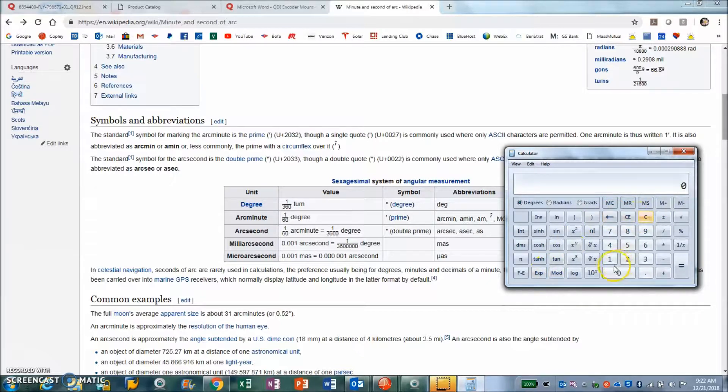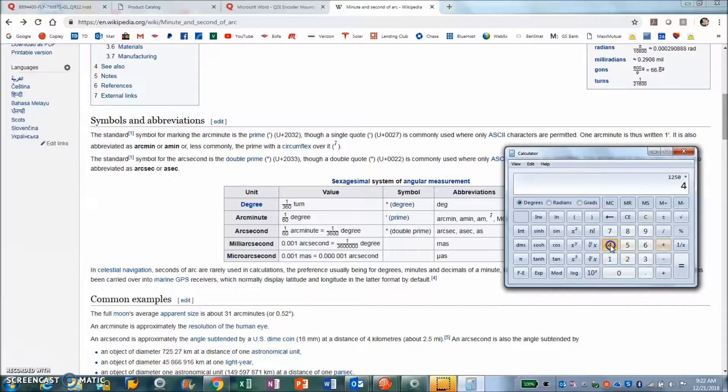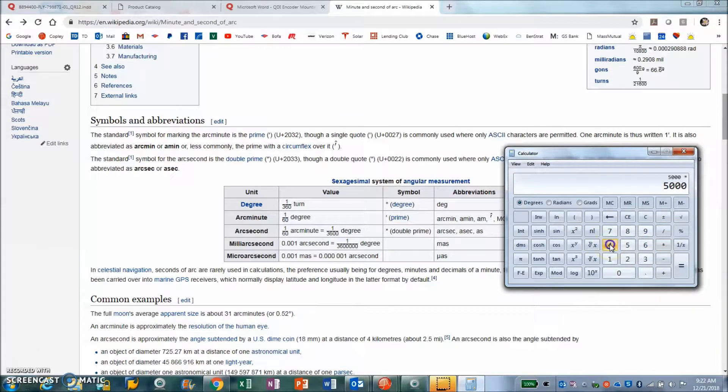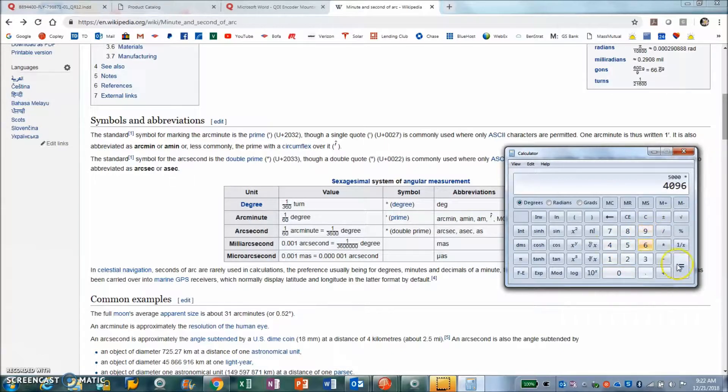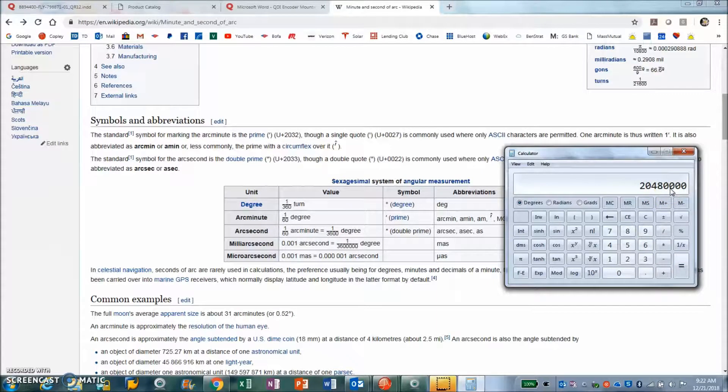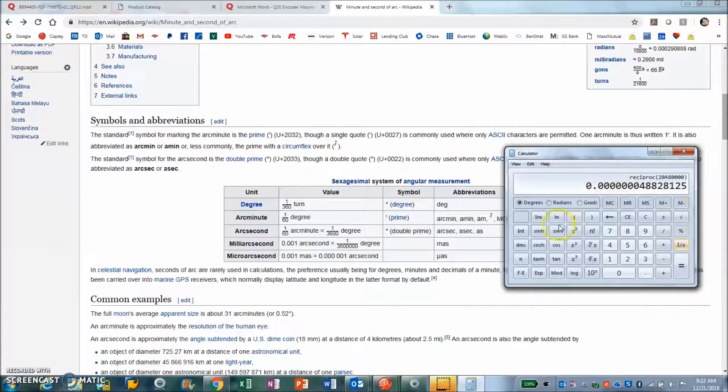If we look at the encoder fundamental of 1250, multiply that line by four we get 5000 fundamental counts per rev, and then times interpolation of 12 bit, only 4096, all Copley drives can do 12 bits, and we've got this really big 20 million counts per rev. I invert that.